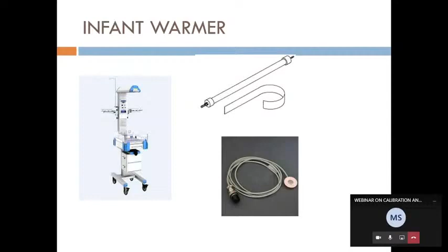If the machine is showing probe fail, you first change the probe. After changing the probe, if it is working, then there was a problem with the probe. How do you check this probe? You take a multimeter, put it in resistance mode, and check the resistance of the temperature probe. If the resistance is not okay, then you need to check the cable. This way you can service it. Most of the problems will come with the heater coil or the temperature probe. The only thing you can check is the resistance value. If the resistance value is okay, then the coil is okay, and the problem is that supply is not going. If the resistance value is not okay, then the coil is the problem.